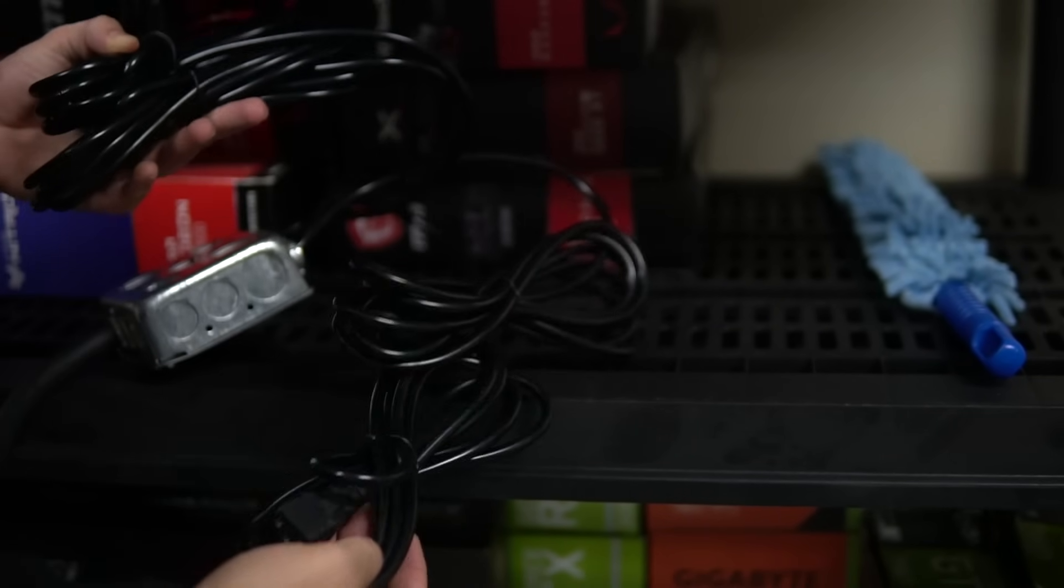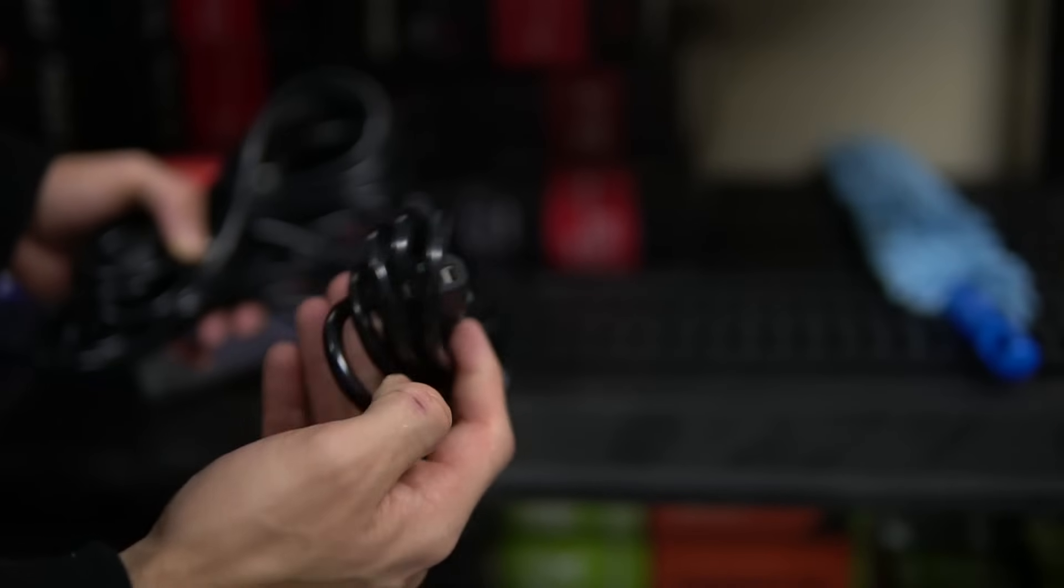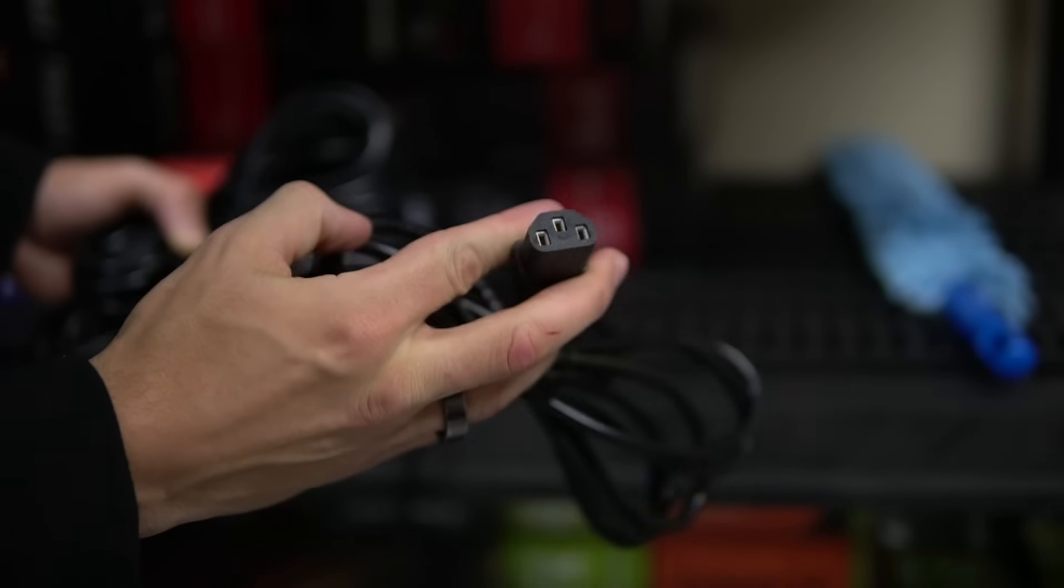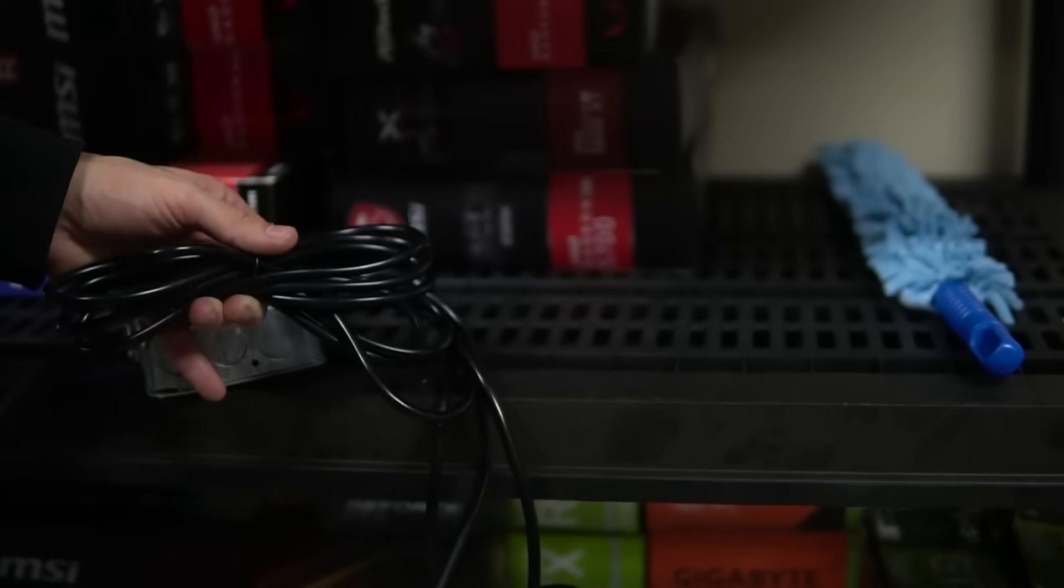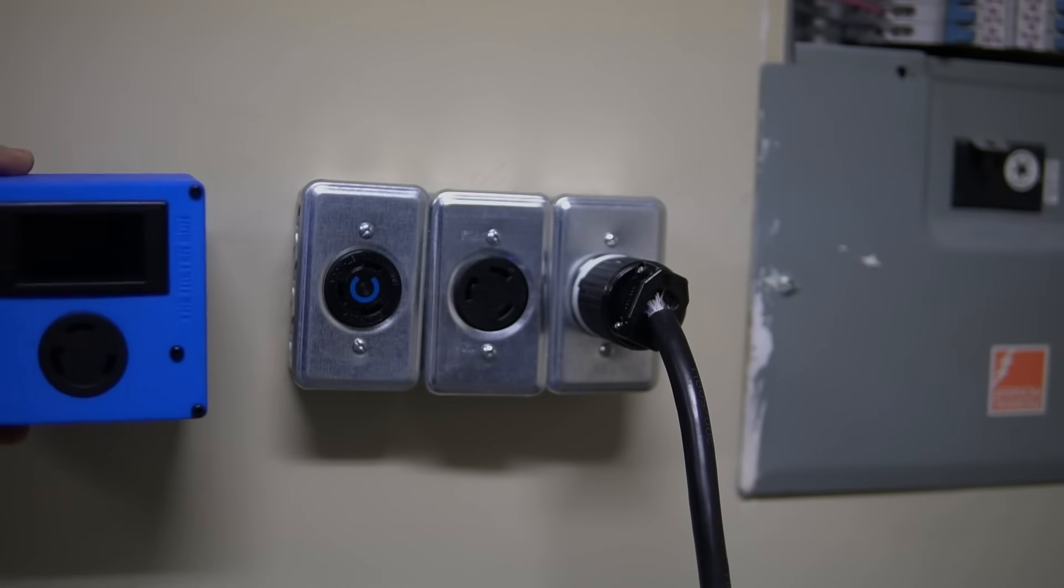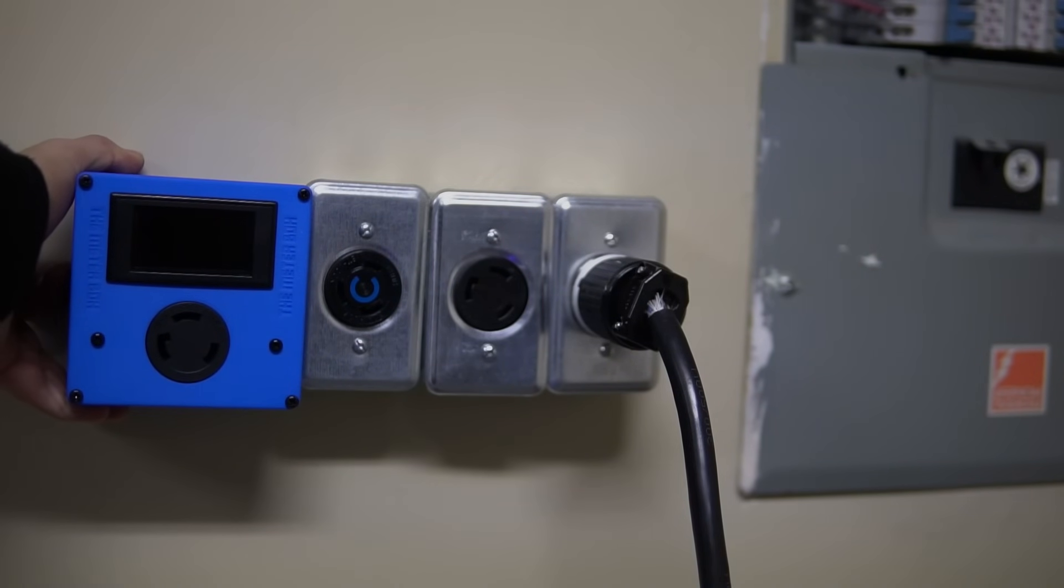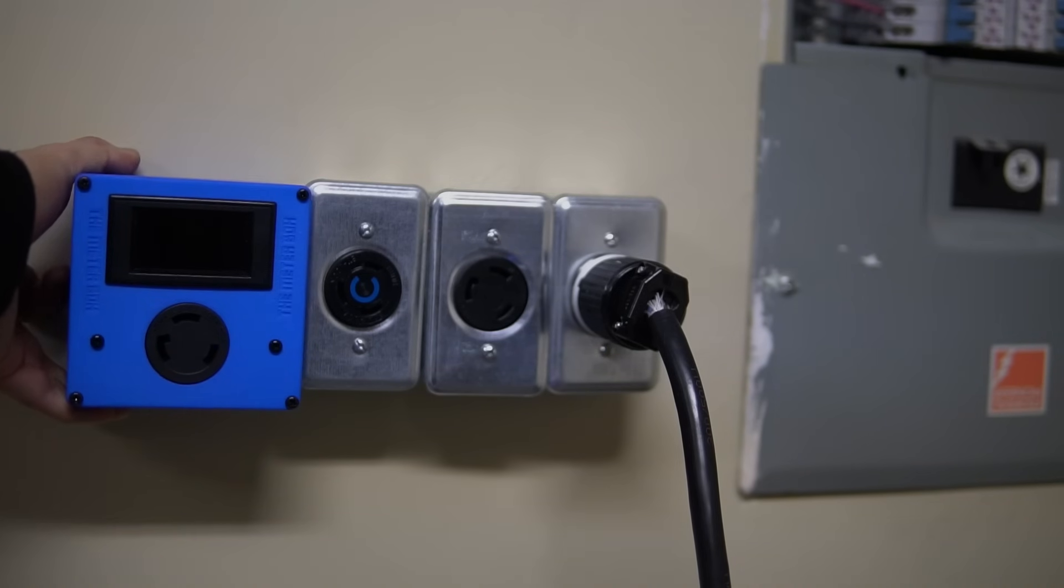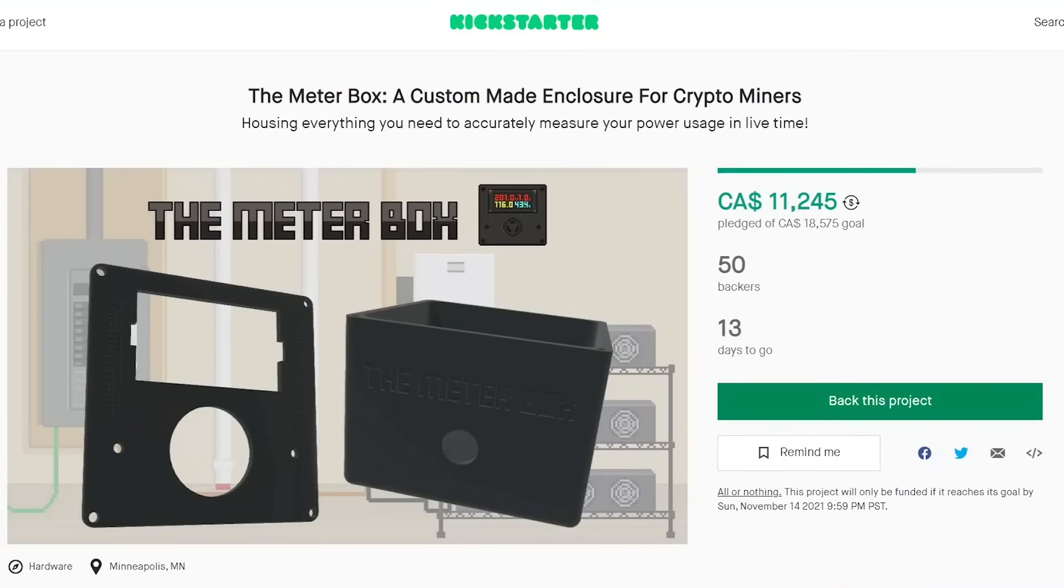It also comes with the cable that connects directly to the outlet. Instead of using a PDU, you'll be using these different cables that come out of this box, which plugs directly into your power supply. So you have a total of four cables that would plug into any power supply. The way you set it up is exactly like setting up a 30 amp 240 volt outlet, so you just have to wire it up properly from the inside and then it's good to go.